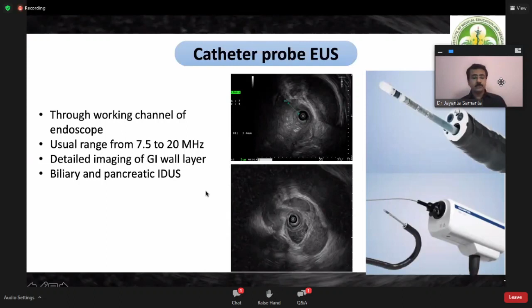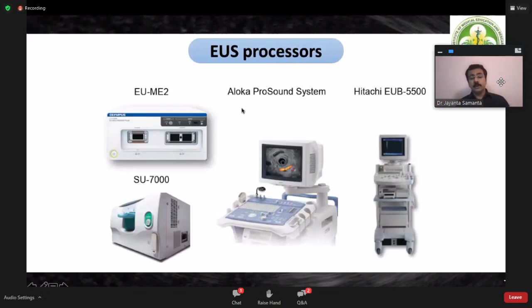The usual range available for these mini probes is 7.5 to 20 megahertz, sometimes even 30 megahertz. They give a detailed imaging of the GI wall layers, and these are also used for biliary and pancreatic intraductal ultrasound. So the same probe can be used both for imaging of the GI wall layers, let's say for small strictures or a small submucosal lesion, and for pancreatic and biliary intraductal ultrasound. Coming to the basic EUS processors that are available, we have the Olympus EU-ME2, the Aloka system for the Pentax, and the Hitachi system. For all practical purposes, we use the Olympus system of the EU-ME2 or the Pentax system with the Aloka system.